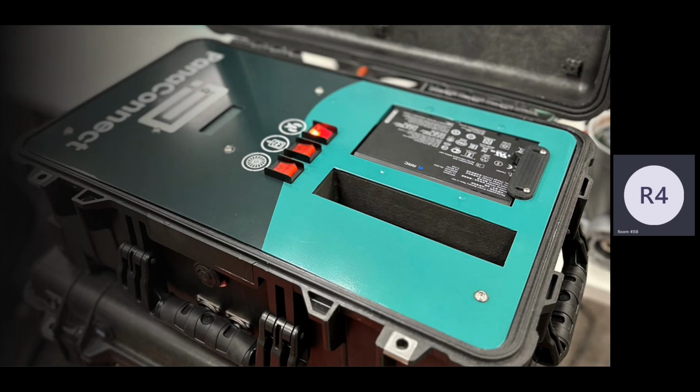If there are any red flags that our engineers are able to determine, say, out of 10 boxes, 8 things check off but 2 of them don't, then we're not going to verify or sign off on those meters. So it might require us to go out to the field, or if it's something that can be replaced or done remotely by us telling the customer what action to take, then we could do that.